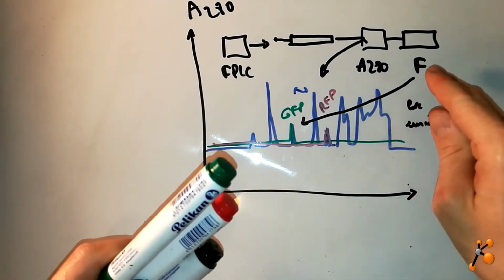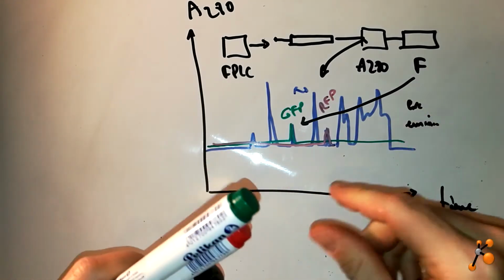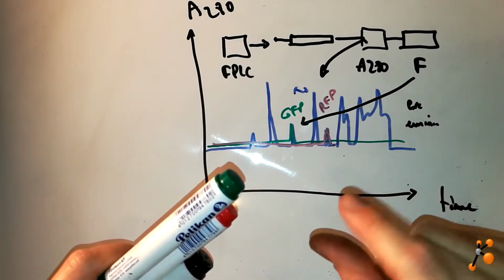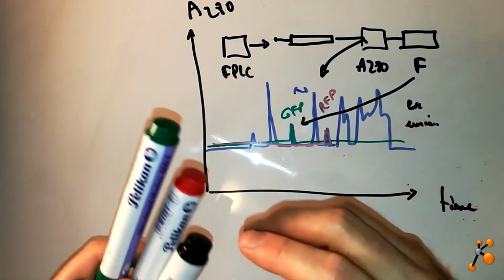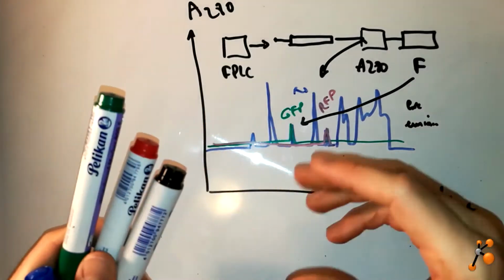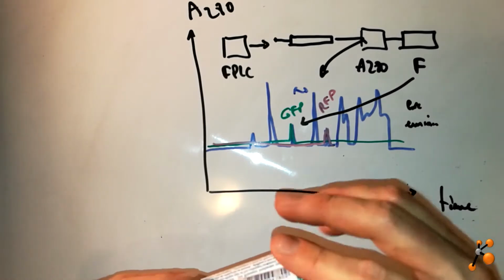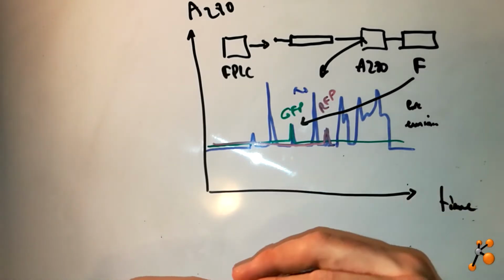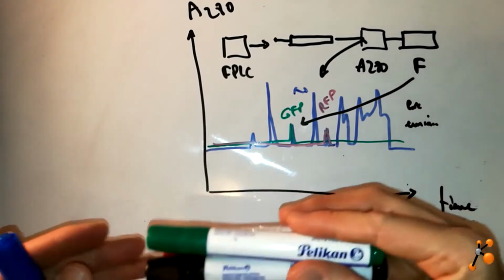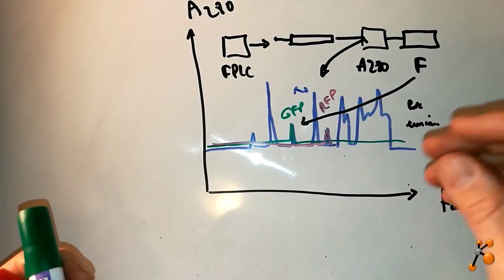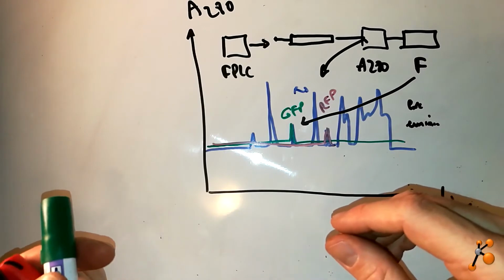So you have a sophisticated fluorescence detector where you can select exactly which wavelength in nanometers you want, and also for the emission. It's really sophisticated optics inside, and it uses very pure light, which gives you the whole range, and then you have a selection of the excitation and then emission by different filters.